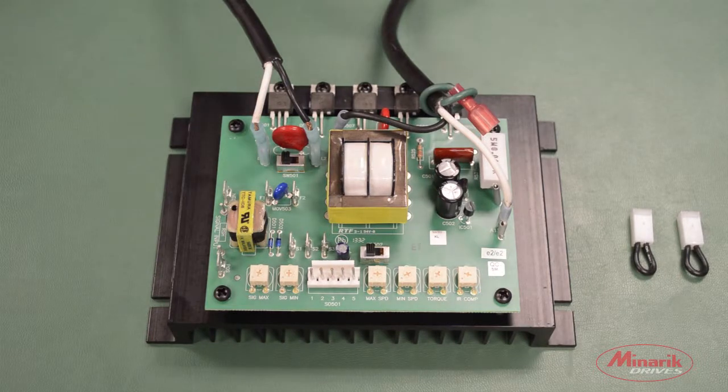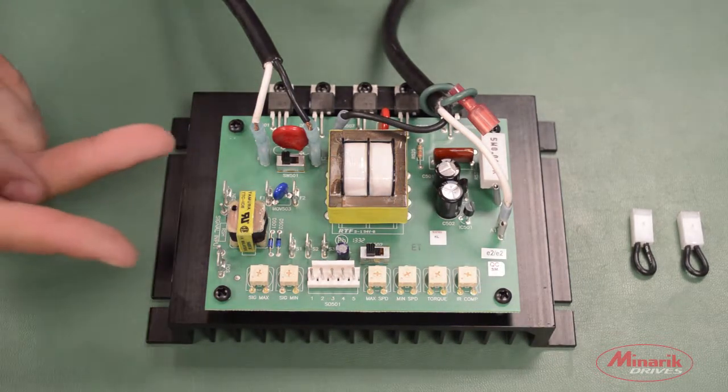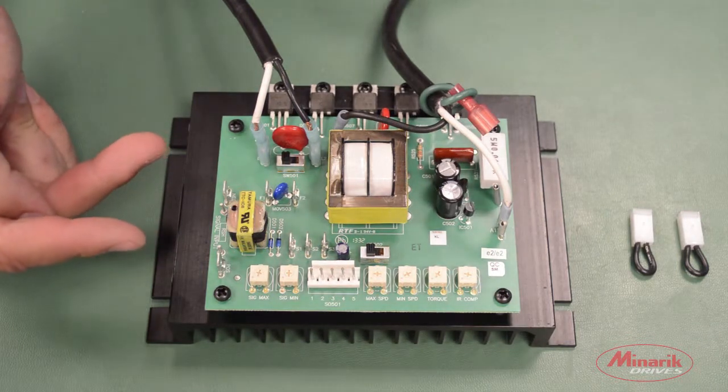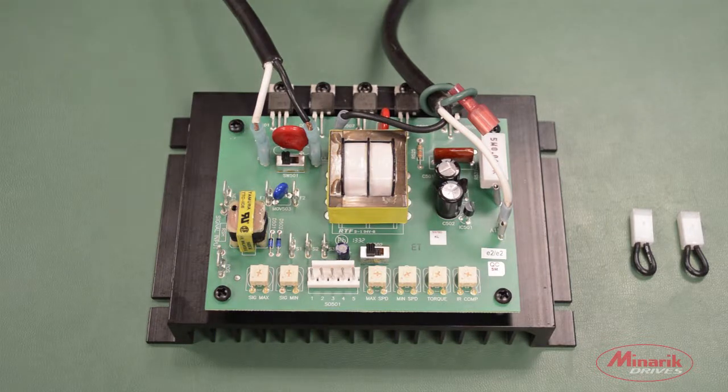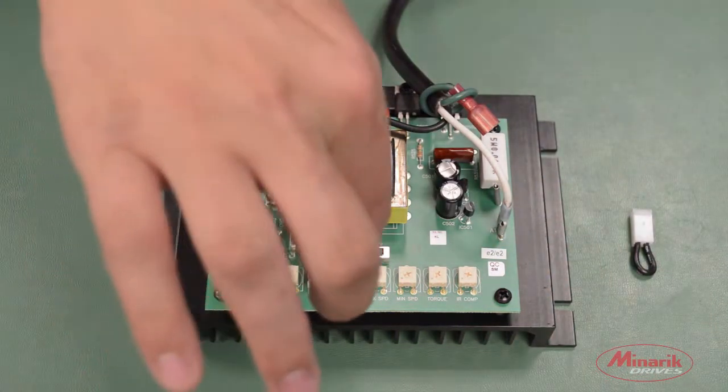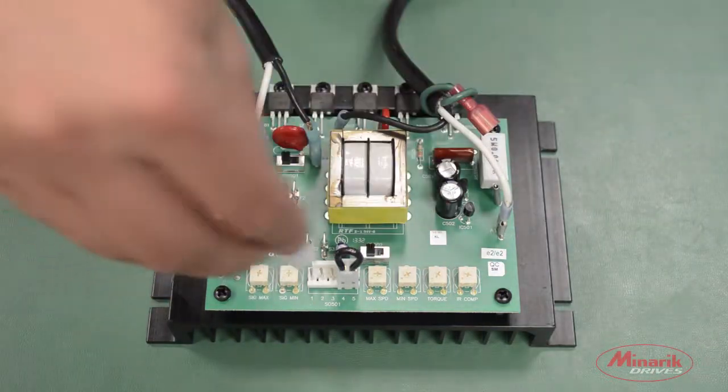The last mode is signal with ratio output mode. In this mode, the drive will follow the voltage input signal but also be proportional to the speed potentiometer. To put the drive in this mode, we are going to use a jumper to short pins 4 and 5 and pins 2 and 3.